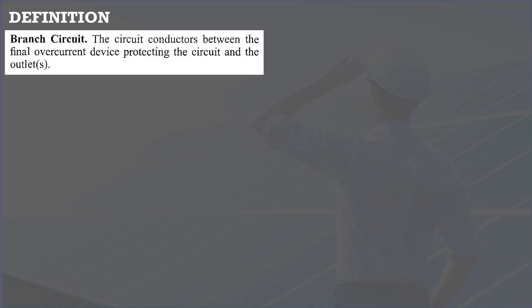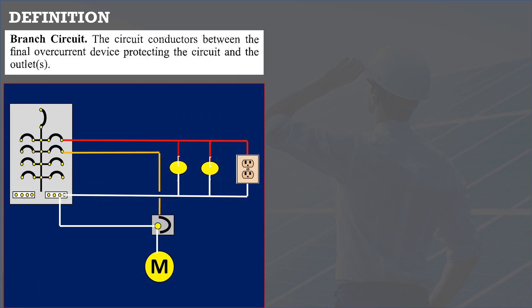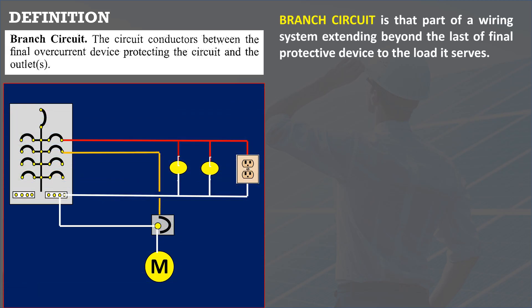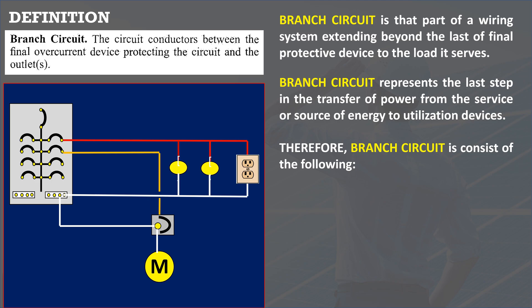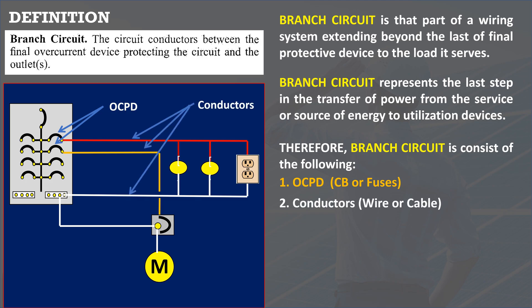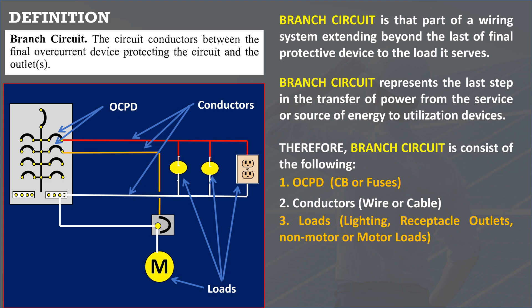In code definition, a branch circuit is the circuit conductor between the final overcurrent device protecting the circuit and the outlets. As shown in the figure, the branch circuit extends beyond the final protective device to the load it serves, representing the last step in transferring power from the service or energy source to the utilization device. Therefore, a branch circuit consists of: 1. Overcurrent protective device, which can be a fuse or circuit breaker. 2. Conductors. And 3. Loads, which can be lighting, receptacles, any non-motor load, or a motor.